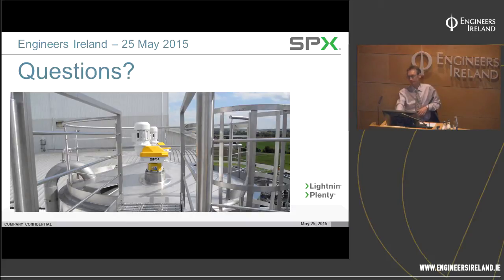I think on slide 14, you might just comment on running cost versus capital cost for different options that you have. So you're talking about a big impeller running slow versus a small impeller for the selection. Yeah, so you'll end up with a range of possible mixers which will all do the job, and you'll typically have a small impeller running fast with a high power and a big impeller running slow with a lower power. And as Martin says, there's an analysis to be done of capital cost, which will mostly come down to the amount of torque you're putting in, because the gearbox is a big part of the cost of the mixer. So capital cost versus running cost, and clearly the high power motor is going to have more running cost in terms of kilowatts of electricity.